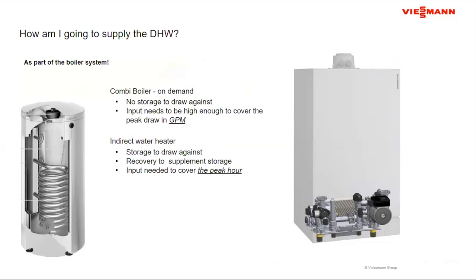So if I'm going to supply the domestic hot water, we've decided we're going to do it as part of the boiler system. So I have two choices, the combi or the indirect. As we talked earlier, the combi boiler is an on-demand method, which really means that there is no storage in the process. So if I have no storage, it has to be able to provide the right amount of hot water on a per minute and per hour basis, based on the firing rate, how much heat I'm putting in there. So when I look at the design of the system, if I'm doing combis, I have to look at it from the aspect that the firing rate has to provide enough gallons per minute into the building so that everybody is satisfied with the hot water, whatever they're using the hot water for.